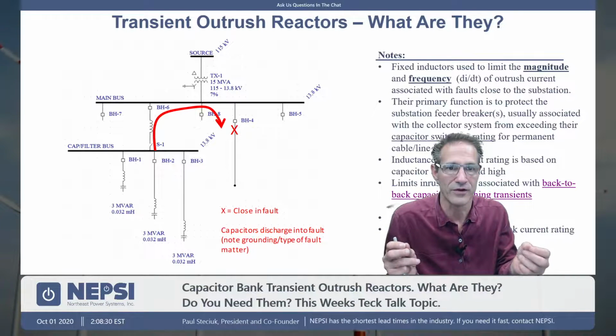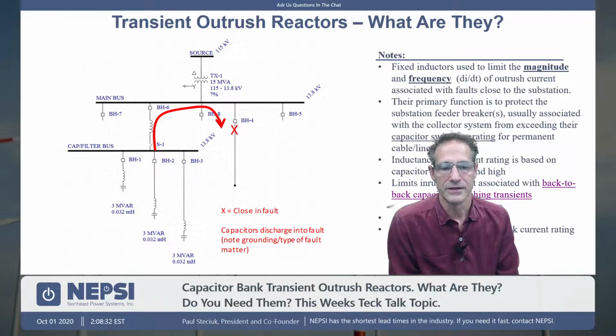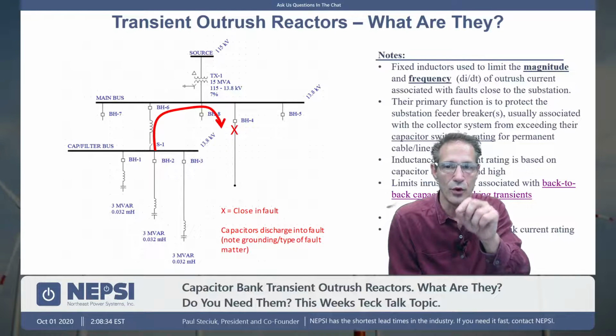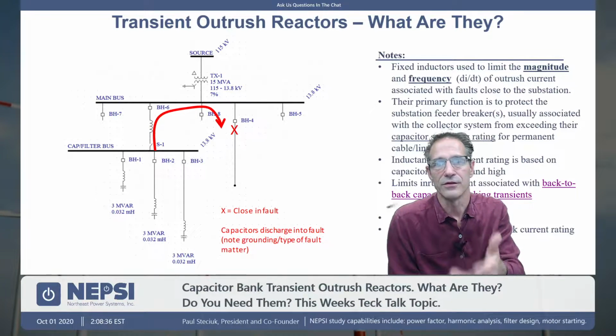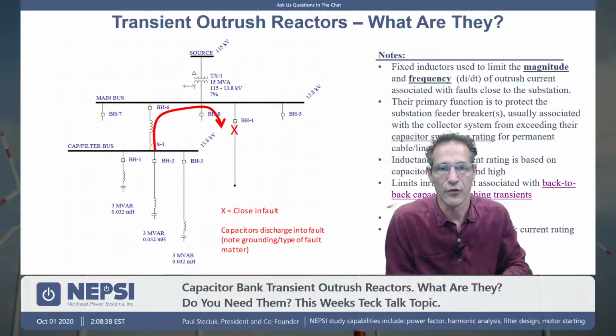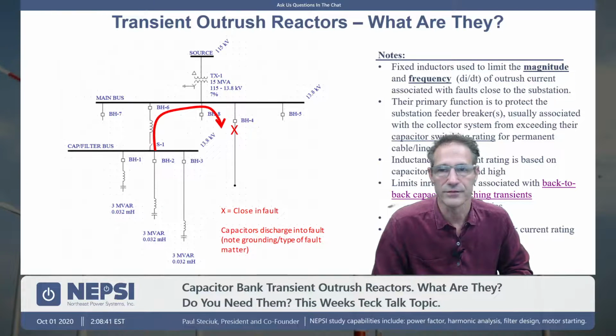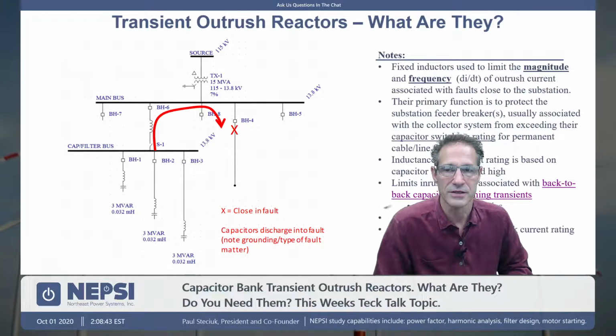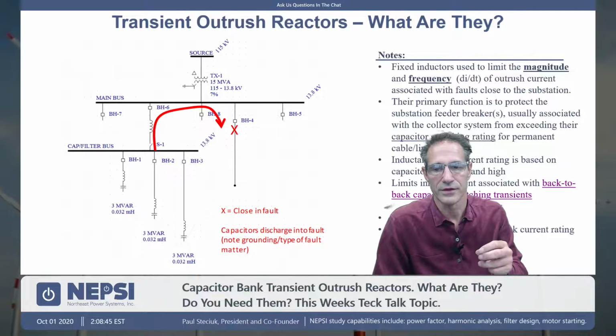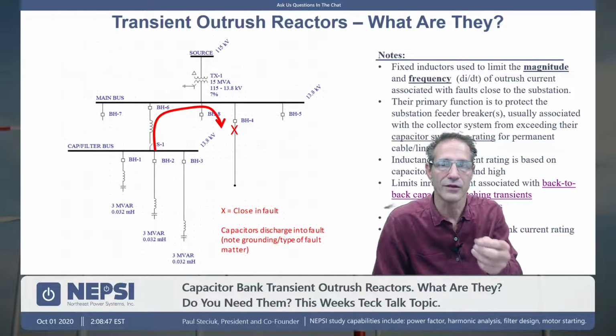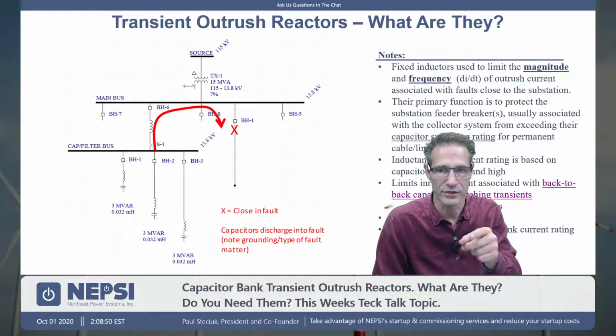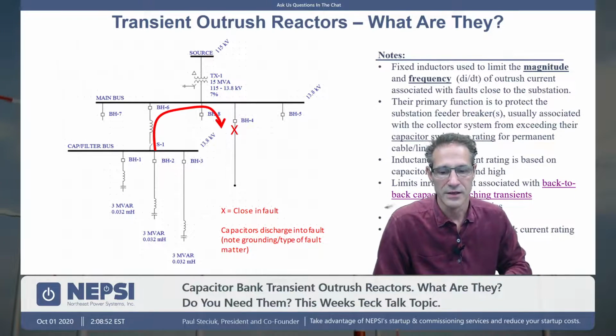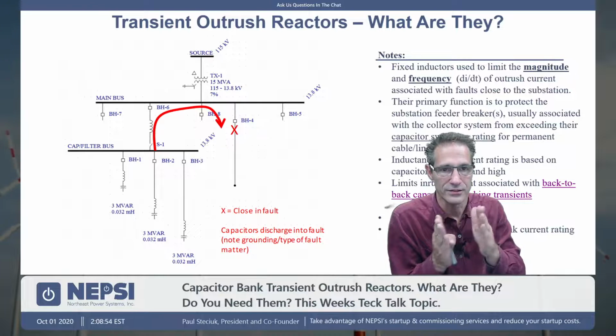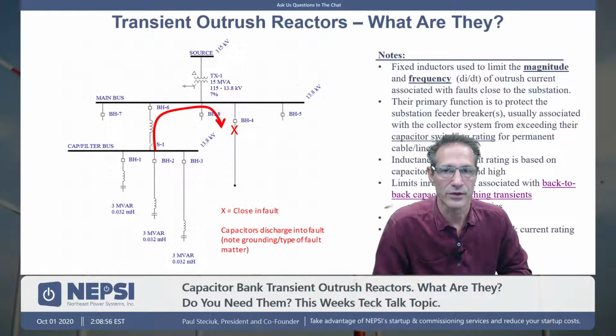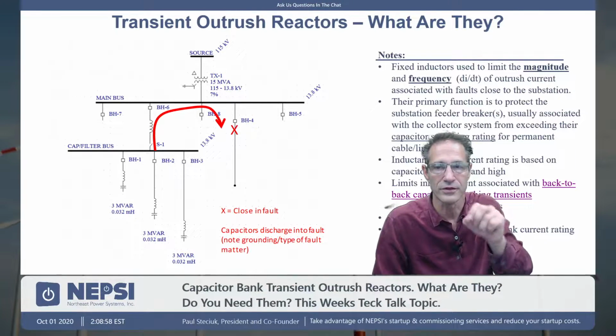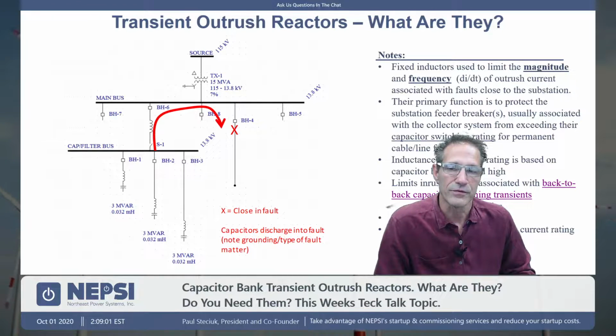You're looking at maybe 0.5 microhenries per foot. There is almost essentially no impedance between the two. So in those situations, we would typically add about 40 or 50 or 60 microhenries between the stages, and that would have an effect of reducing the magnitude of current and also the frequency of current, so the di/dt would be reduced, and we would eliminate that issue of the contacts wanting to weld because of that very high rate of current. So that's the purpose of the transient inrush reactors.